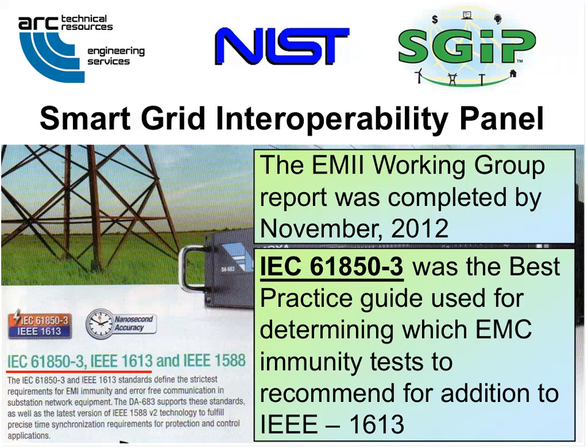The EMI Issues Working Group report was completed in November of 2012. IEC 61850-3, which was in the NIST Catalog of Standards, was the best practice guide we used for determining which EMC immunity tests to recommend for addition to IEEE 1613, as there was a new edition coming up, IEEE 1613.1, which was an extension of the existing IEEE 1613 from 2009. These two standards, 61850-3 and IEEE 1613, were already widely used in industry, as shown in their advertising, so it wasn't felt that these were a burden to American manufacturers.